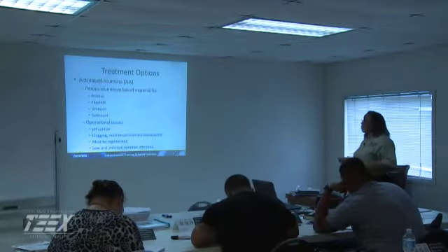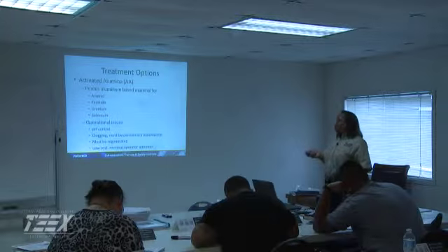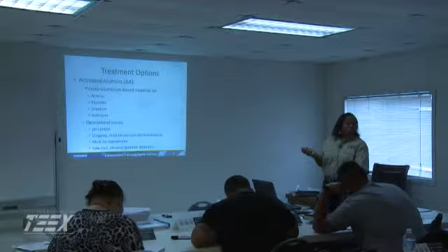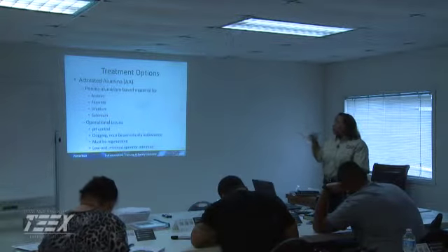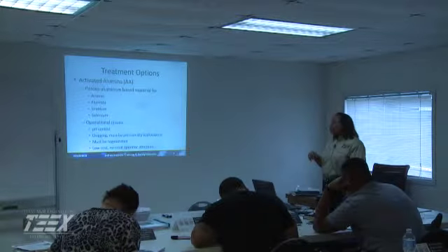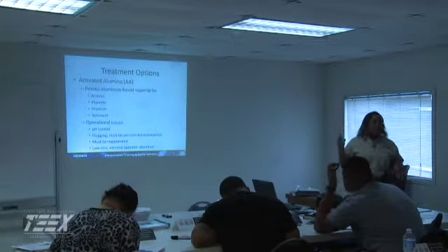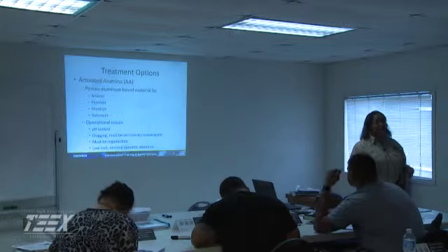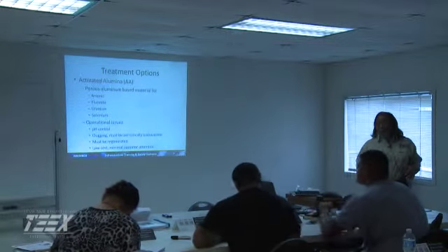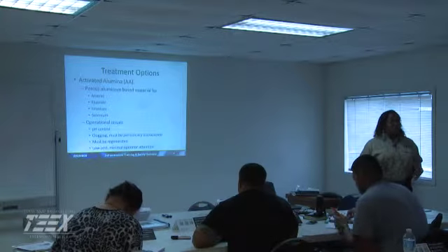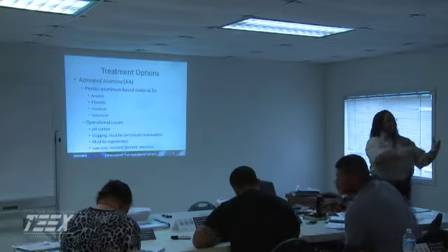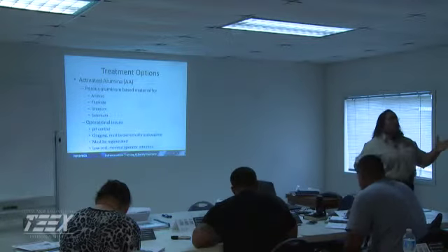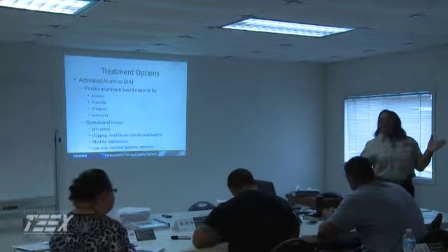Some of the operational issues with your activated alumina is pH control. Most of your treatment processes are very much pH dependent. There's also clogging of these beds, and they must be periodically backwashed. When you all get your microfiltration system up and going, periodically you're going to have to backwash it. What do we mean by backwashing? Because I'm sending water through this membrane, sending water through this membrane, sending water through this membrane. What's going to happen over time?